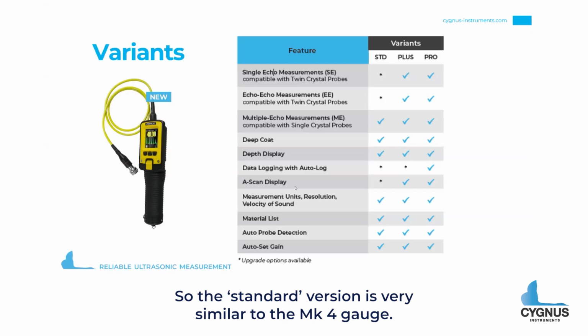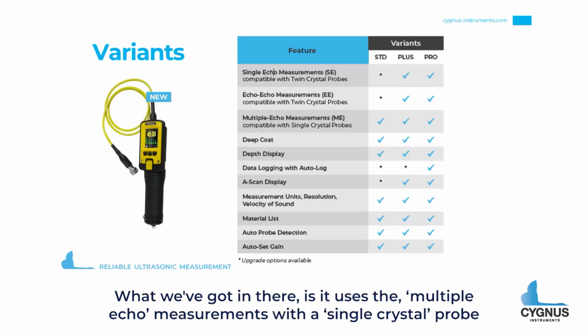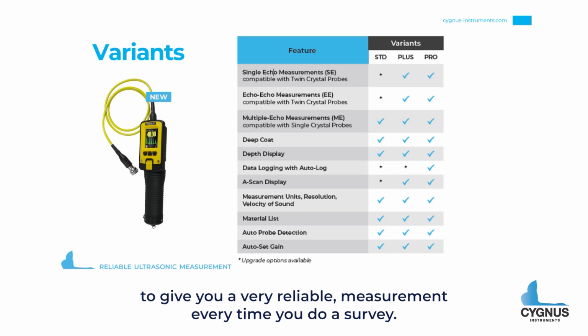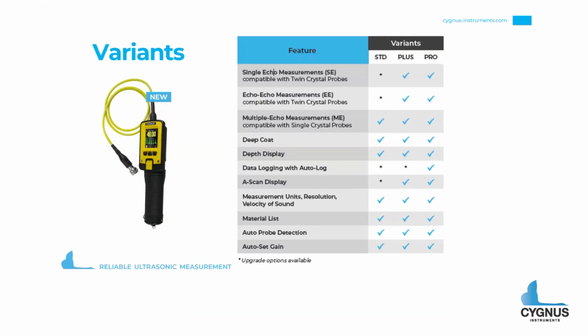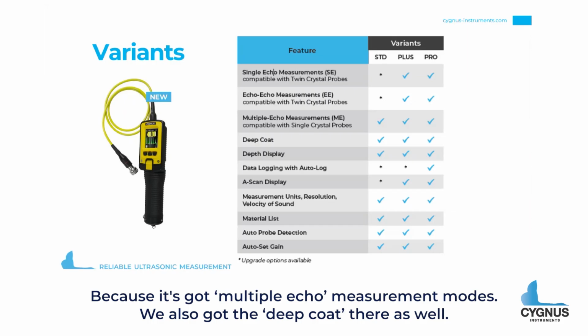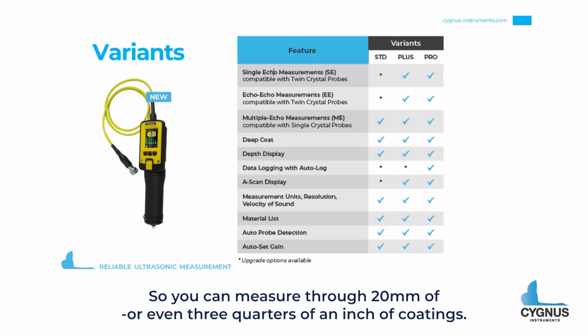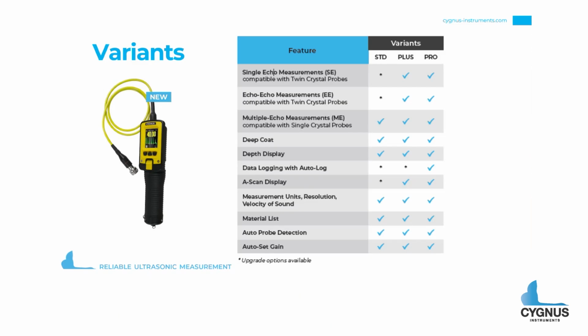So the standard version is very similar to the Mark IV gauge. It uses multiple echo measurements with a single crystal probe to give you a very reliable measurement every time you do a survey. Because it has multiple echo measurement modes, we also have the deep coat there, so you can measure through 20 millimeters, or even about 3/4 of an inch, of coatings.